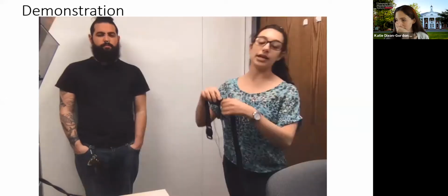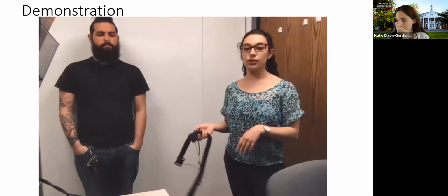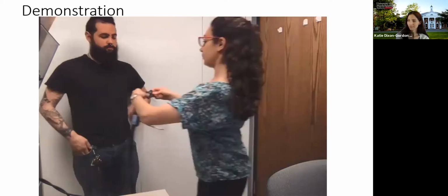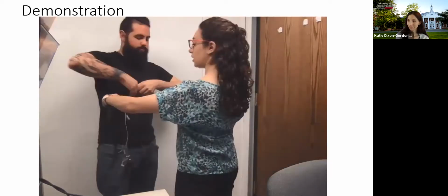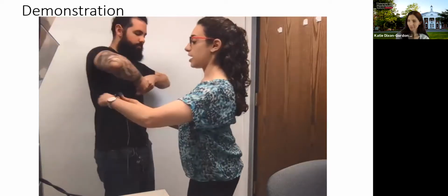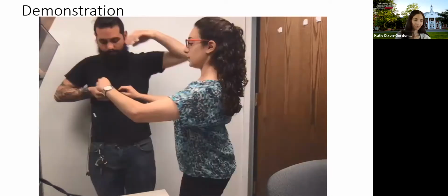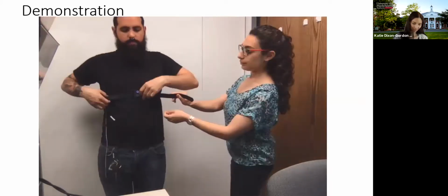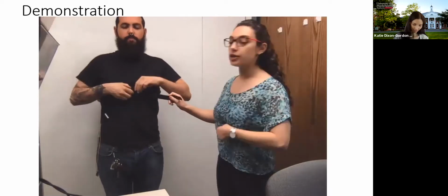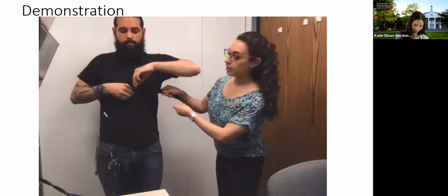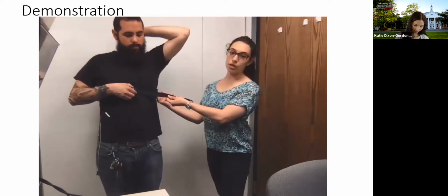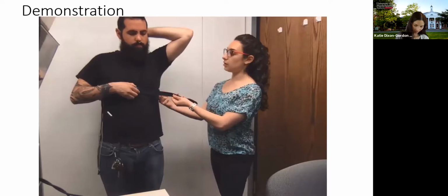So we're going to start off by attaching the respiration band to our participant. So you want to make sure that the band is going around the sternum, and we're going to start off by having the buckle placed in the center of the sternum. So I'll ask you to hold that in the center, and then we're going to wrap the band around your body and filter it through the buckle. So we always want to make sure to keep the buckle in the center of the sternum. And you want the band to be relatively tight. You should be able to fit 1 finger underneath the band comfortably, and 2 fingers should be a bit tight. So how does that feel? Pretty good. Right there. Okay.